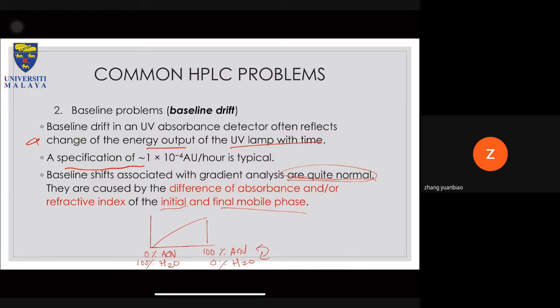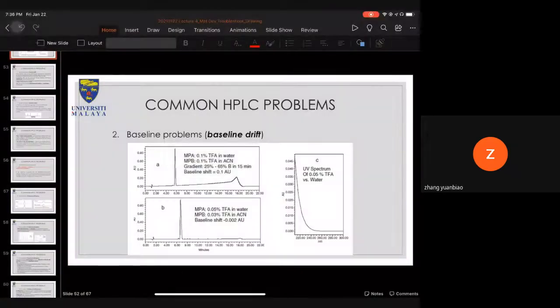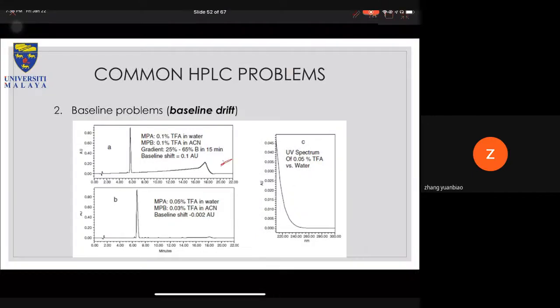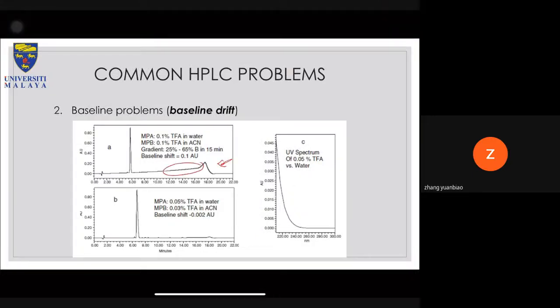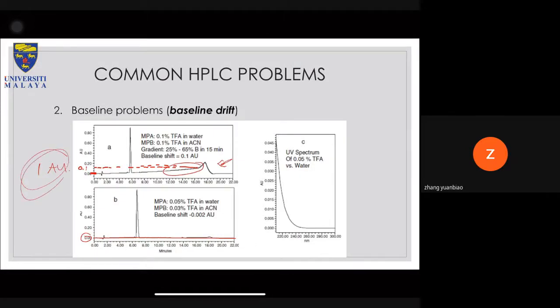So how does a drift look like? So this is how a drift looks like, okay? Without drift, normally the baseline stays close to 0. With a drift, you can see that initially the baseline is close to 0, but after your run has finished, that one is about 0.1. Okay, so this is what we call a baseline drift. A small drift is typically okay, but once your drift becomes too big, say for example, if your drift is close to 1 AU, then something is wrong with maybe your detector or your system altogether.